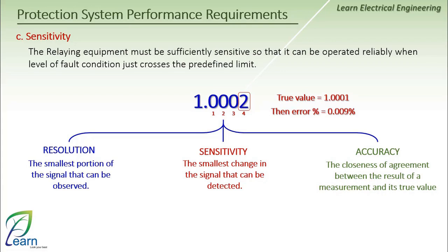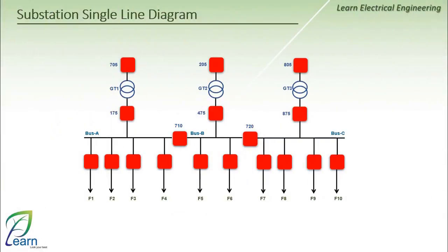We have a single line diagram for a single bus single breaker scheme with bus sectionizers, consisting of 3 incomers connected to 3 buses, and there are 2 bus sectionizers. Let's assume all the breakers were closed.